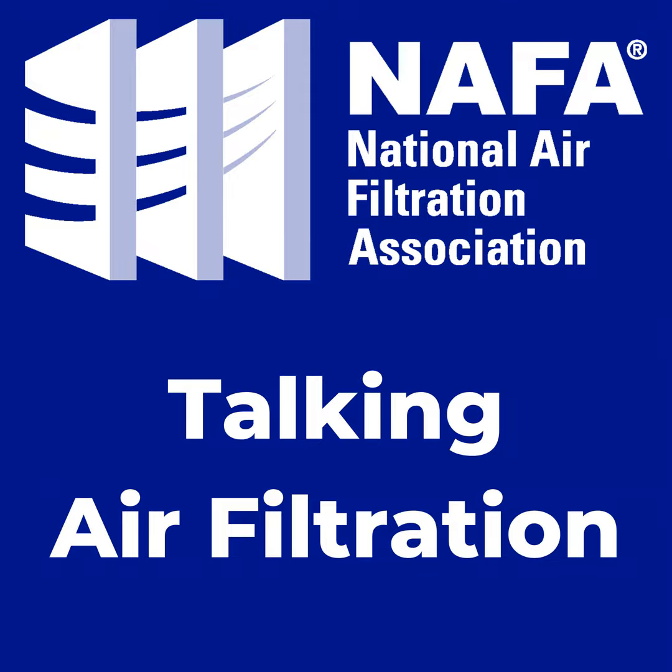And with the nanofiber media, again, we took that PTFE and loaded it with dirt. I try to explain to people that a nanofiber substrate is basically considered a membrane. It's like a wall. It's not depth loading. It's designed to just catch stuff and not let it go through. So there's no depth to it. You can't really have a dust loading performance with it. So we need to design better media with better dust holding capacities above that nanofiber.